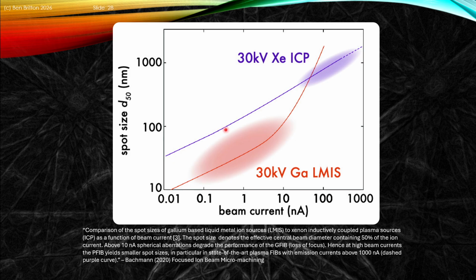We notice that the spot size is typically a lot smaller for our gallium FIB. That enables us to be more precise in how we cut objects as we're FIBbing them. The xenon FIB typically has a larger spot size. It's up at the sort of 10 to hundreds of nanometers, depending on how we set up the instrument. It can be made a bit smaller if we want to optimize it. But here we can effectively use xenon, and we'll see this a bit later, but xenon is a large and heavy noble gas, and so it's very effective at sputtering. Gallium is much lighter, and it can form alloys or amalgams with certain systems, and so that's one of the reasons why you might use the two different source types here.